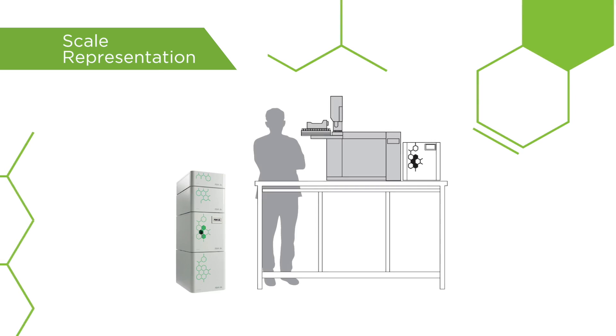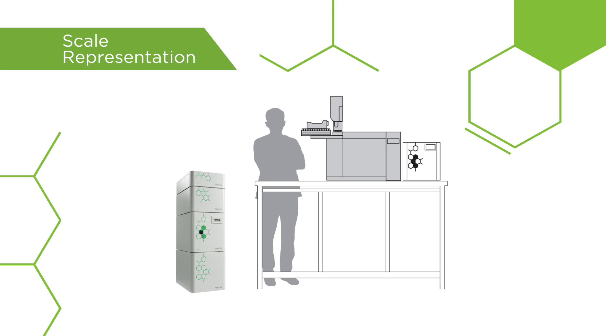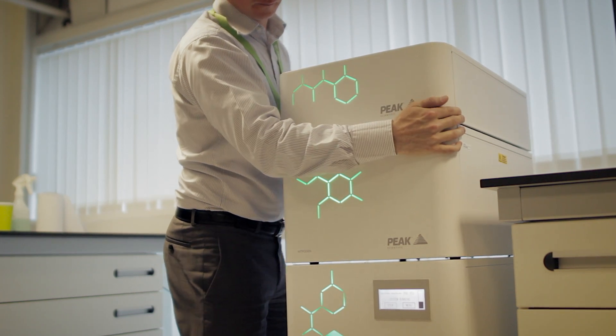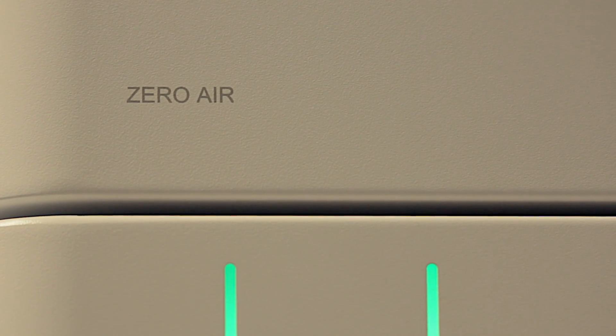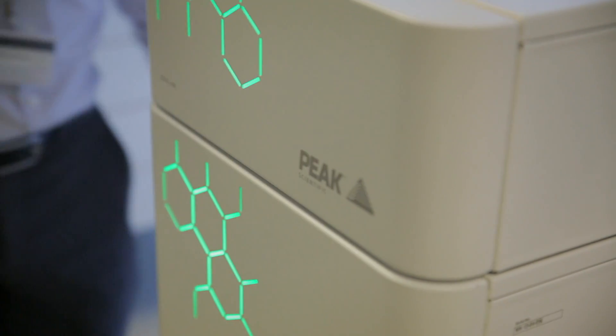There are real potential space savings for labs who get a precision stack compared to using cylinders, but you can also use them individually. So if you only require zero air or nitrogen or hydrogen, you can simply get one of those units.